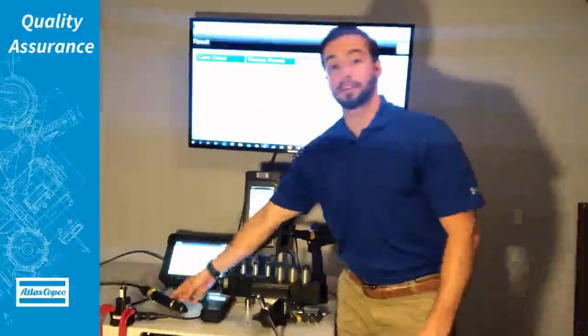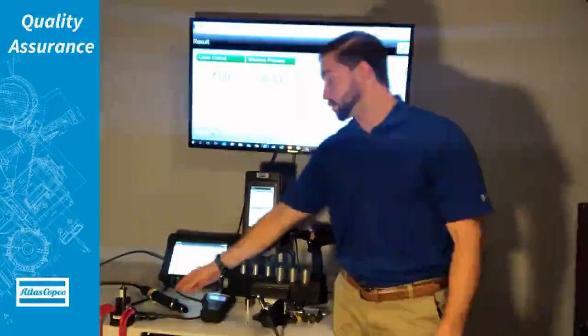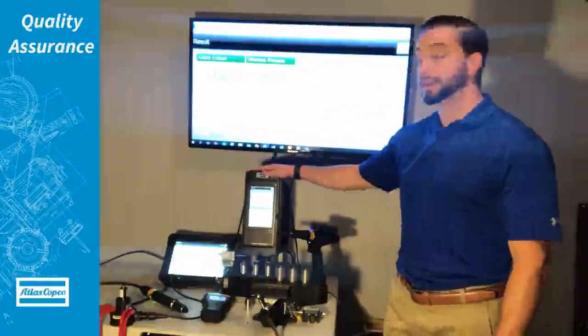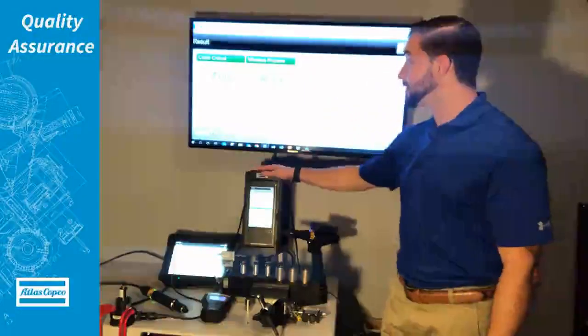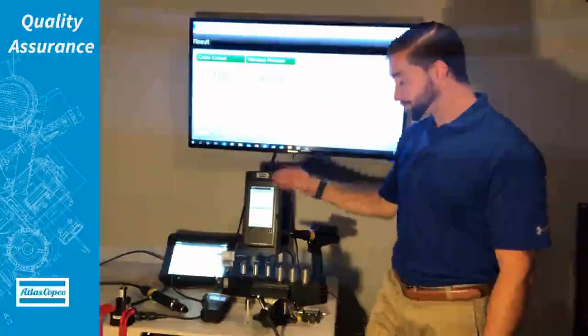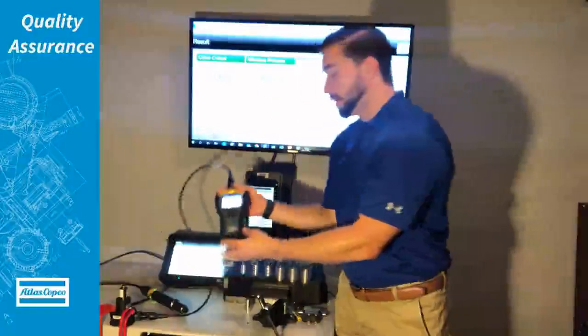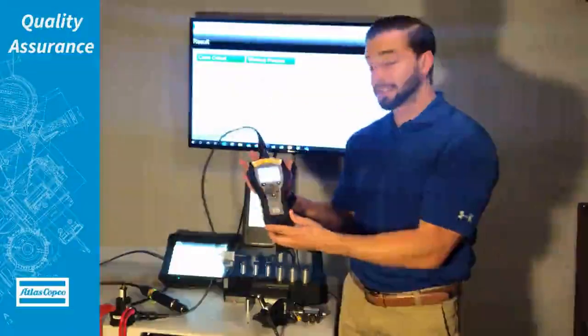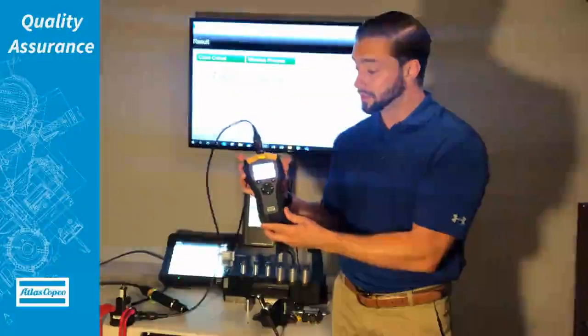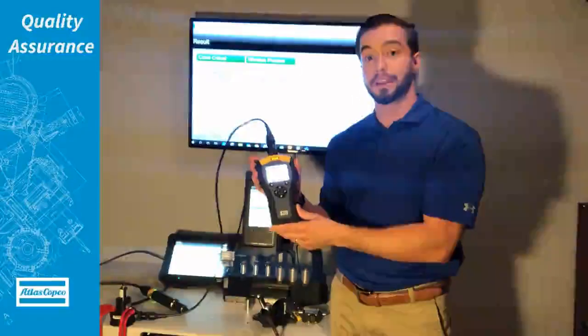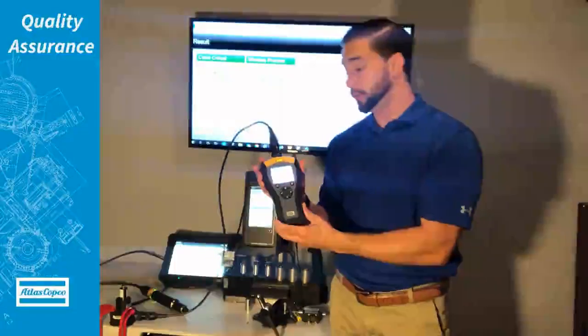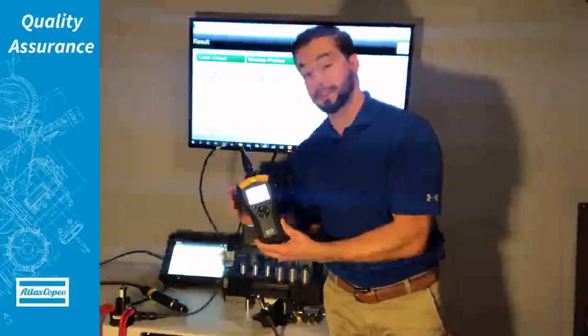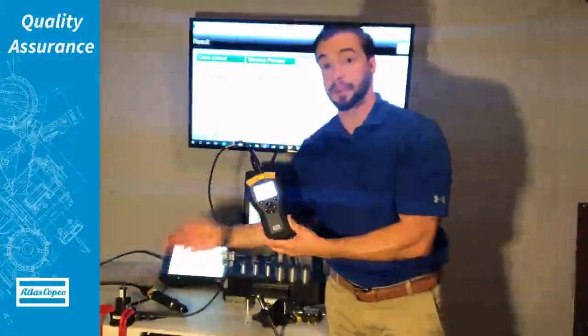We're getting results not only from the internal transducer of the tool which is being shown here on the controller, as you can see that's 7 inch pounds. Then on our STA 6000 as we can see here, this is the display off the external transducer which would be in this case the SRTTB.